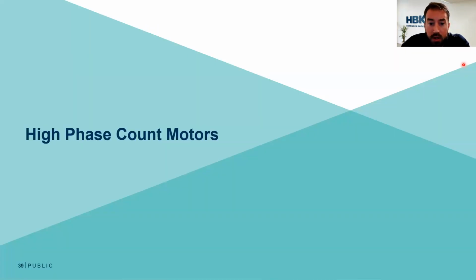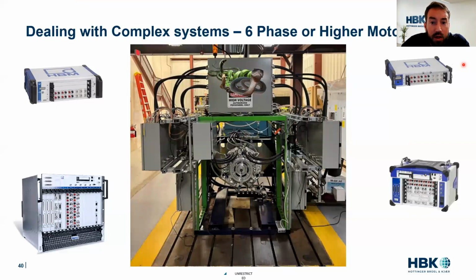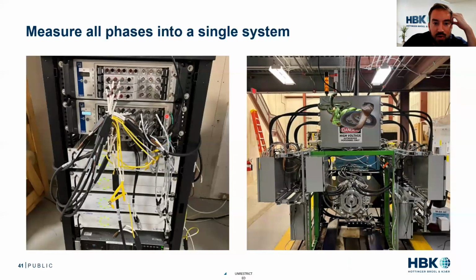Speaking of high phase count motors, here's an example of a customer doing a significantly high phase count motor. I won't give an exact number, but it is greater than 15. We have a wide variety of measurement chassis for handling this type of measurement, because now we're looking at a space where traditional instruments might need 2 or 3 of them to measure this, plus scopes, plus data recorders. Again, we're simplifying that test setup by bringing all of these measurements into one place. Their measurement setup actually has 2 of our systems daisy chained together. They don't always need to use both at the same time, so they have 2 of them. They can connect them together, view all of that data in one location, make all of those measurements, electrical and mechanical, in one location, and characterize their motor from prototype to production.